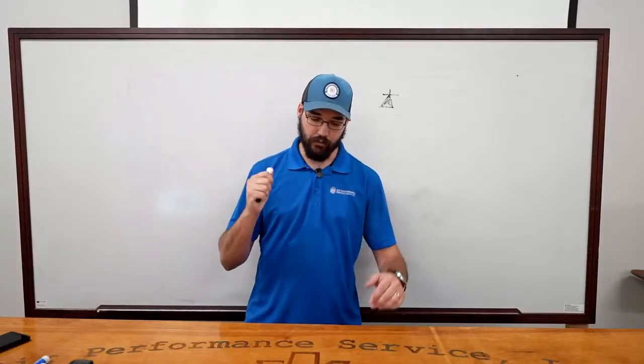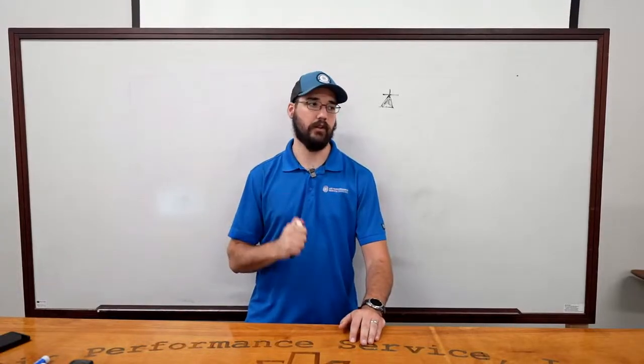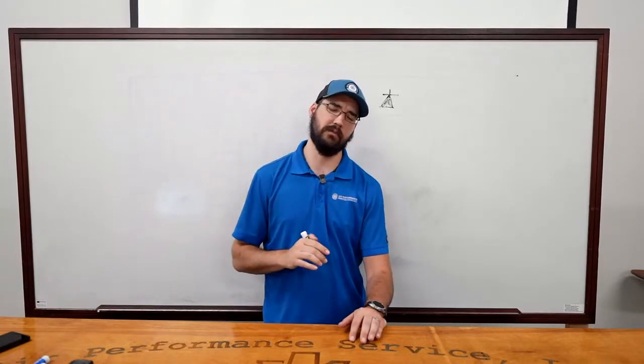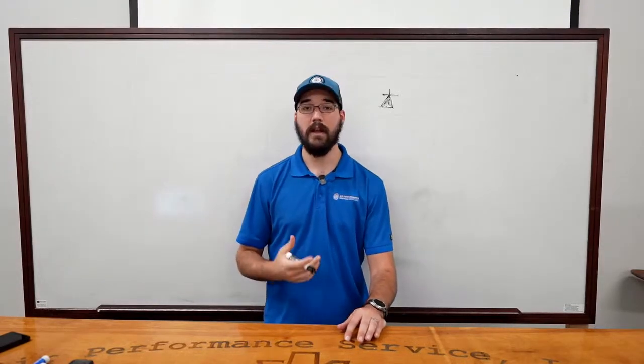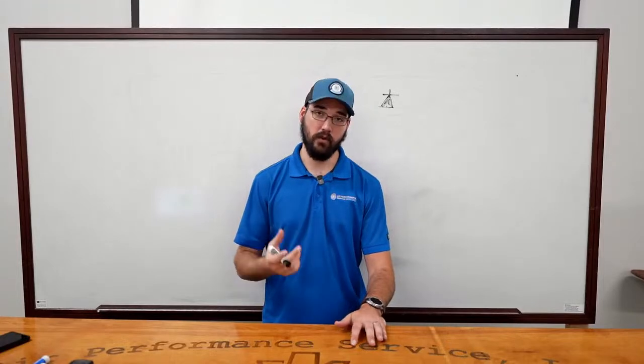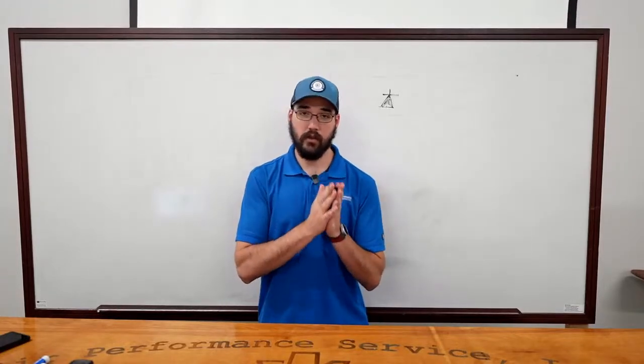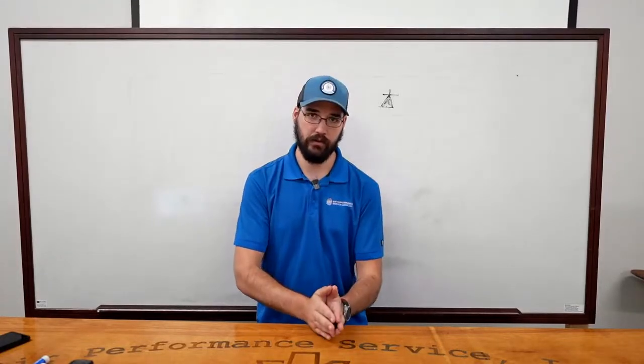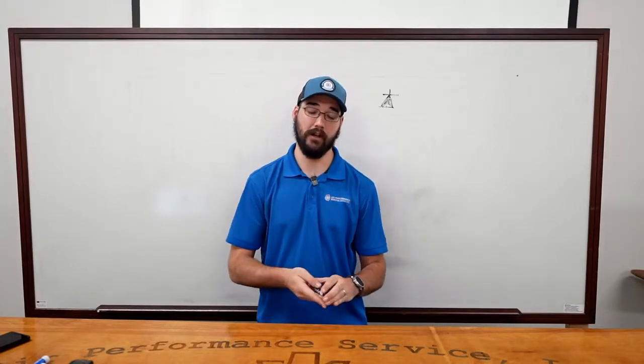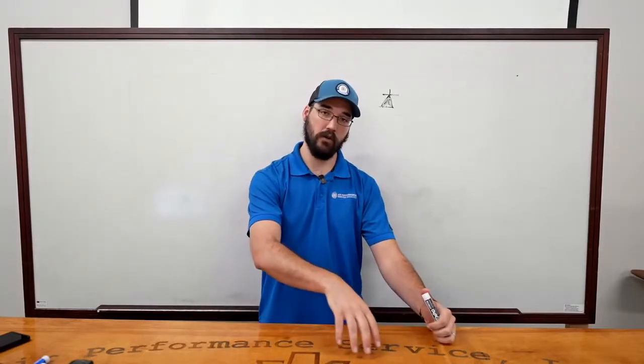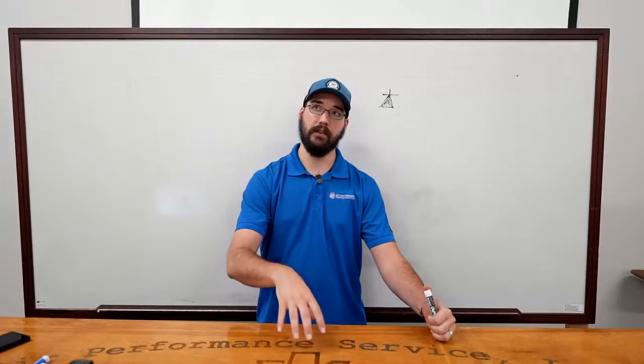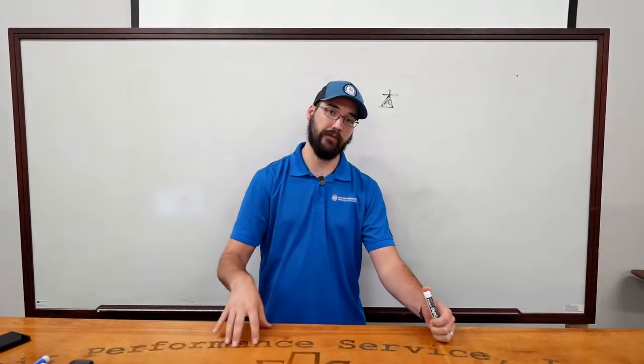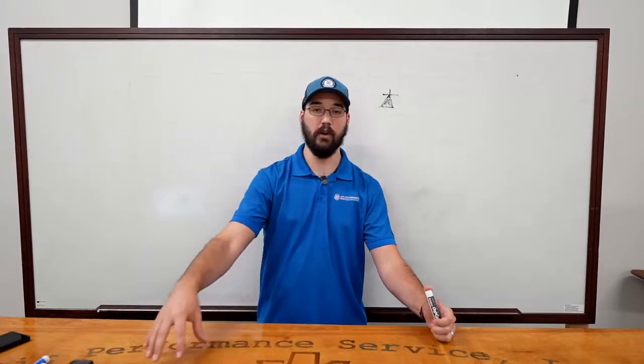Rolling beyond that, I really recommend pay attention to the alarm codes. Not everything on these machines is going to generate an alarm, but a lot of the time they will. And those alarms will go miles to help you sort through what's going on. And sometimes there are alarms that trigger where the workflow for that alarm will lead you to other problems.